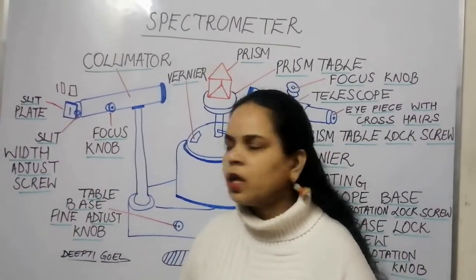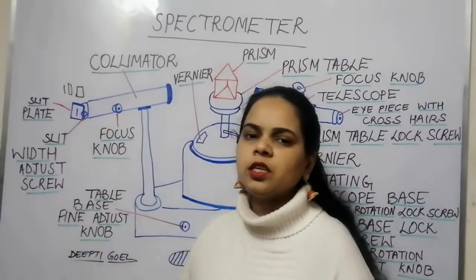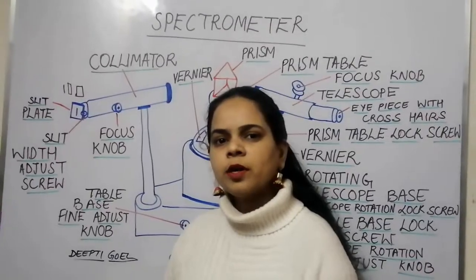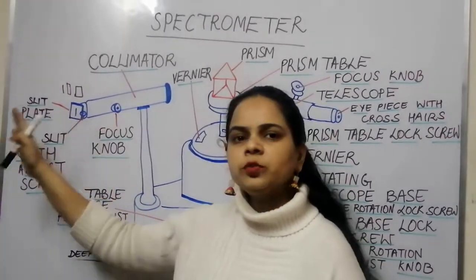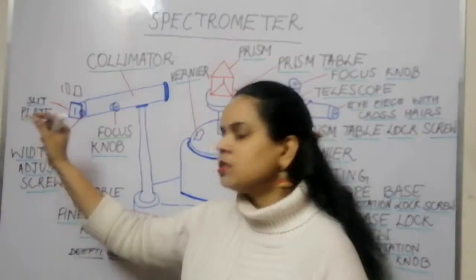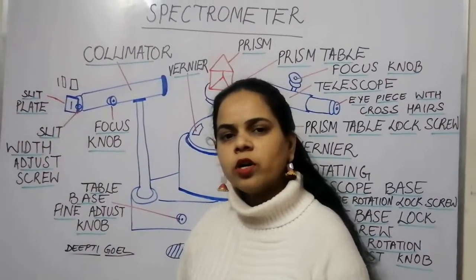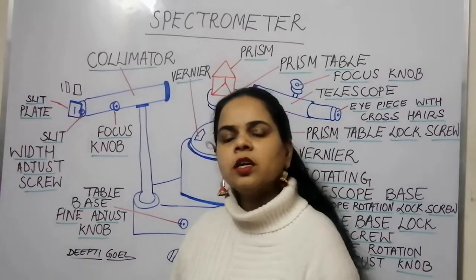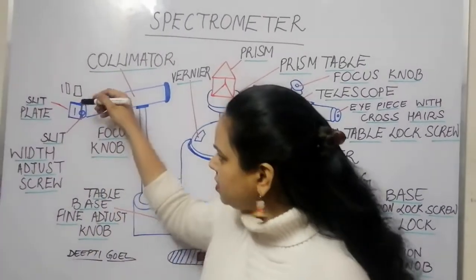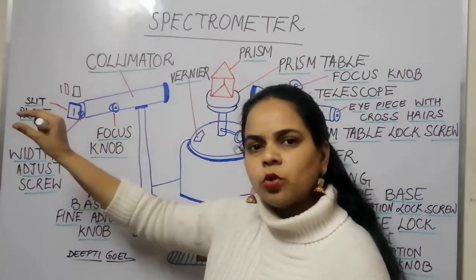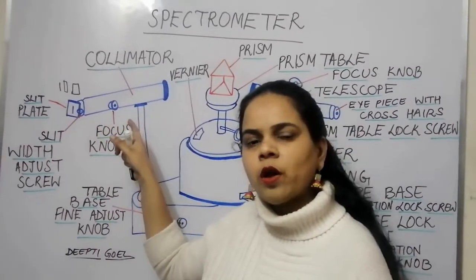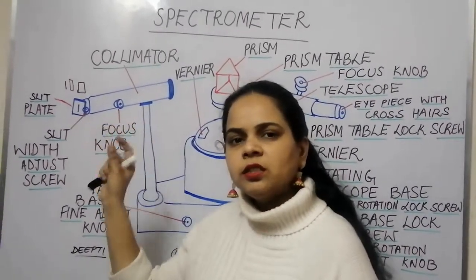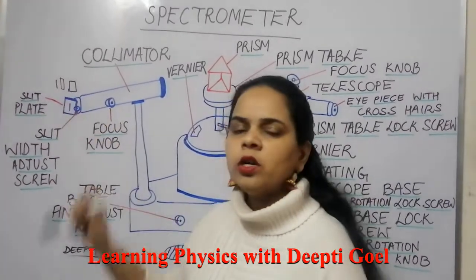The collimator always points towards the source of light, such as a sodium lamp or mercury source. Since the light beam diverges in all directions, the slit plate allows only a narrow, rectangular beam to enter the collimator. The slit width screw adjusts how much beam width is permitted to pass through.